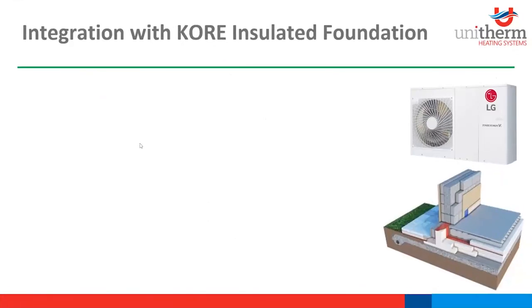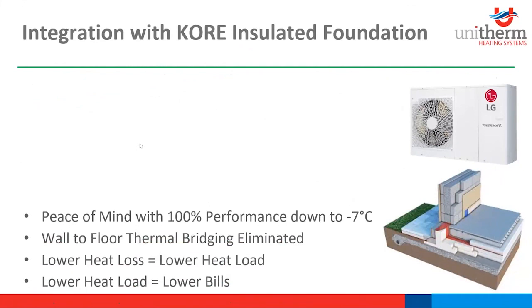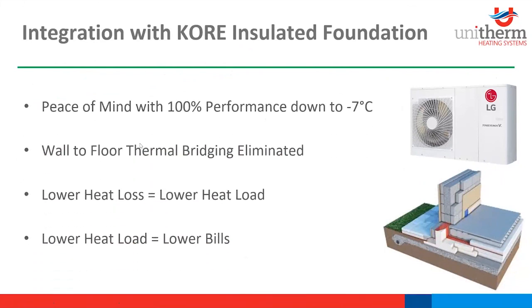So I suppose this is what we're getting to here. The integration of the LG Therma V and underfloor heating with KORE's insulated foundation. As I said, complete peace of mind on these cold winter days with the LG Therma V, as you're guaranteed 100% performance down to -7 degrees. With KORE's insulated foundation system, as Andrew said, exterior wall to floor thermal bridging is basically eliminated. This gives your underfloor heating great relief at external walls and takes pressure off the system in those colder north-facing rooms as well. As floors and external walls are big contributors to heat loss of a building, we've considerably lowered the heat load to consider, which lowers the required heating capacity of the heat pump and therefore brings down capital costs and running costs.